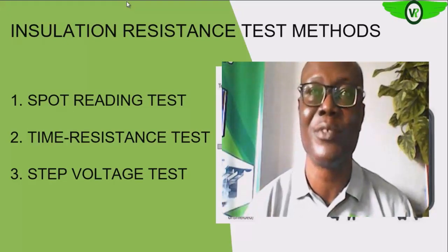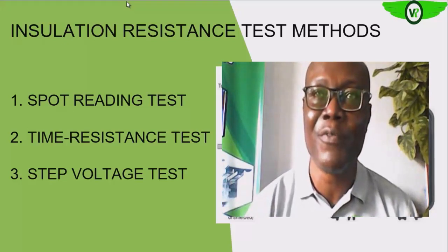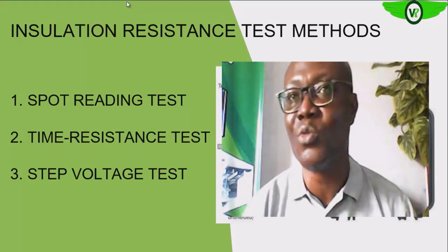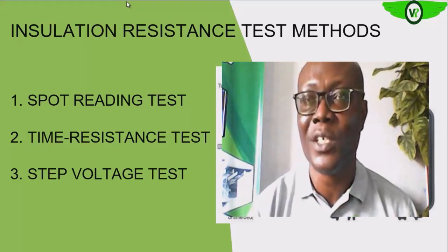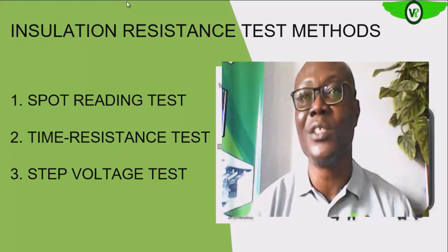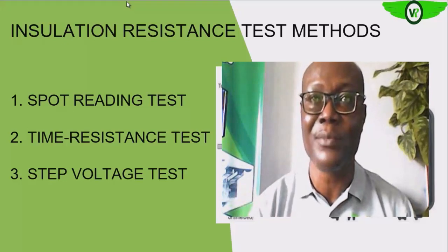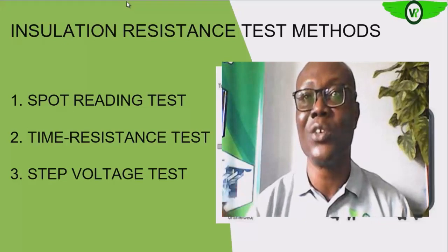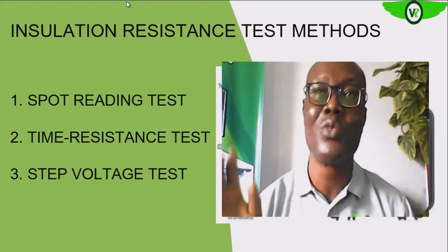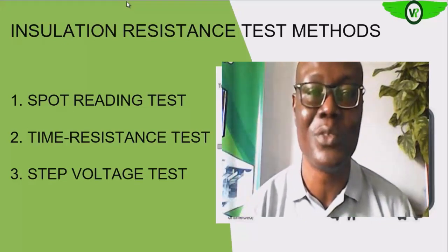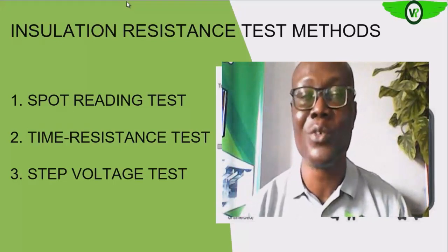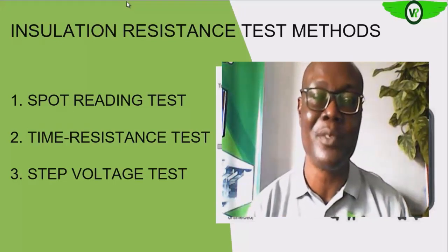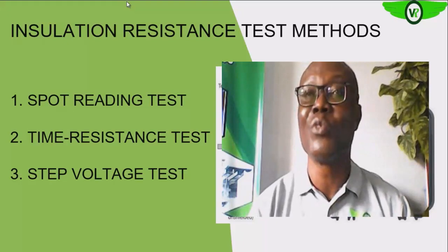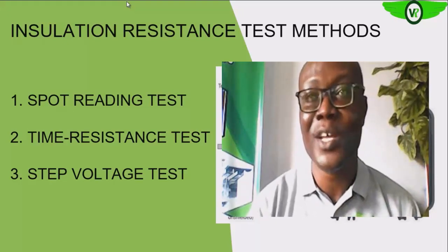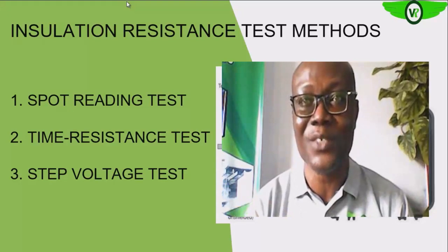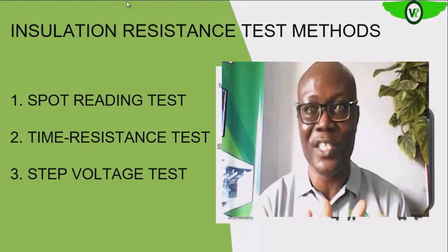We increase the voltage. Maybe for the first reading, we inject 200 volts or 100 volts. The second reading, we inject like 500 volts, 5 times the initial one. Then the third reading, we inject 2500 volts, okay? And we may also go further as the case may be, okay?